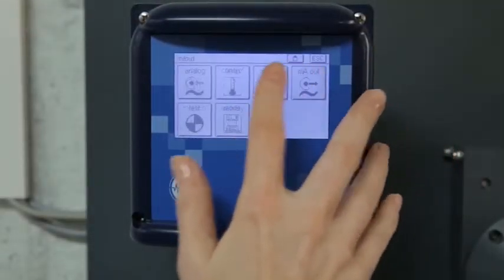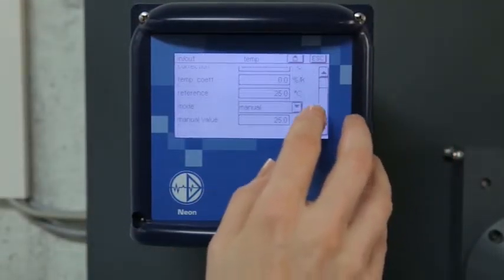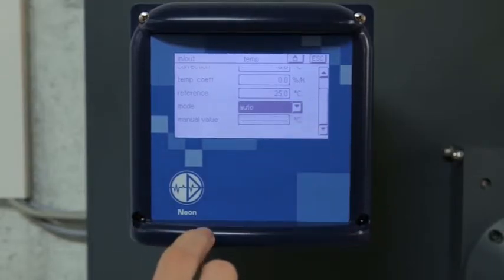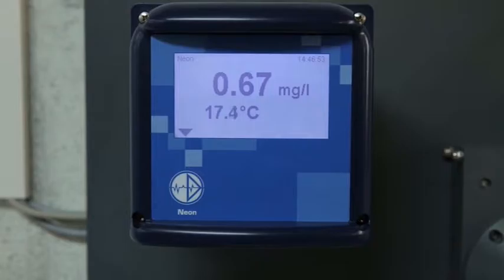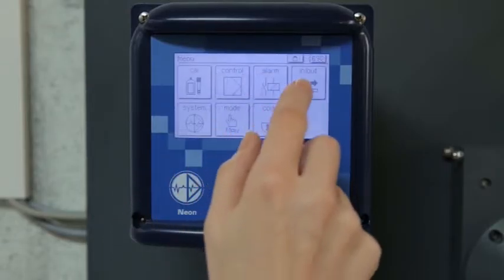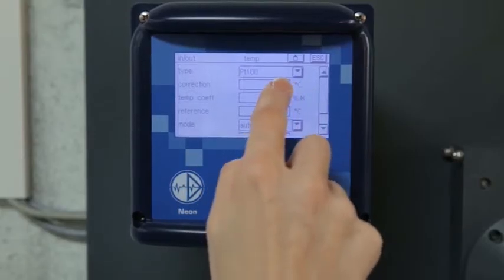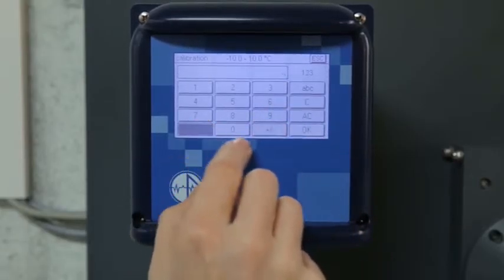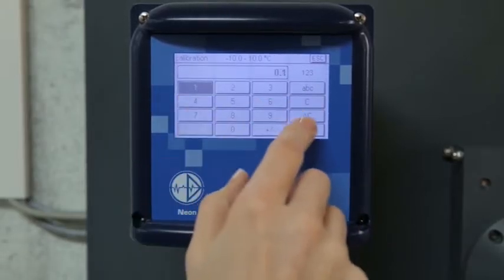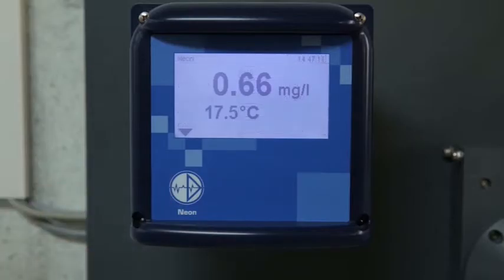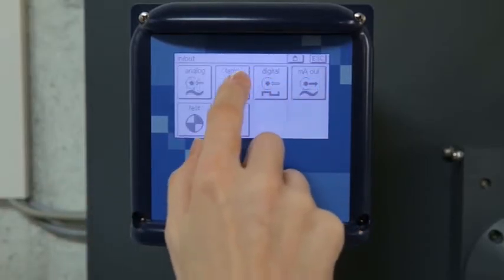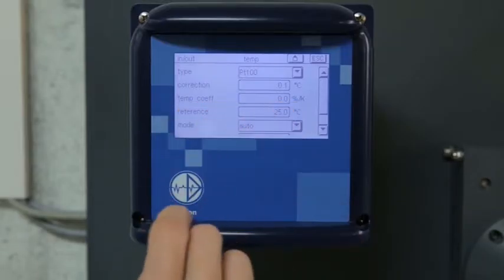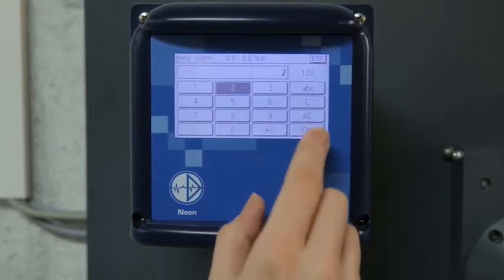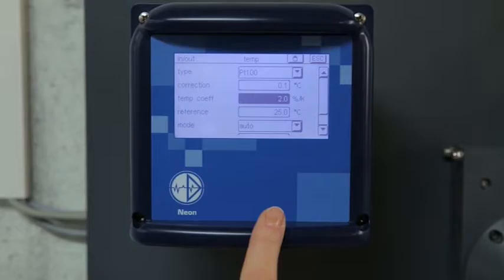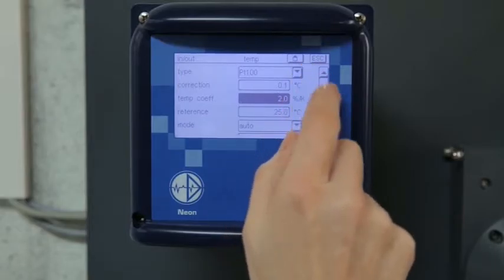If a temperature sensor is connected, set the temperature mode to Auto to get the reading. If the measured value deviates from the expected value, you can correct the value in the menu. If you didn't connect a temperature sensor, you can set the temperature value manually. If you want to use temperature also for compensation, you can set a temperature coefficient in % per degree Kelvin in the temperature menu. A coefficient of 2% per degree Kelvin has proven useful for many applications. You can also set the reference temperature for compensation.